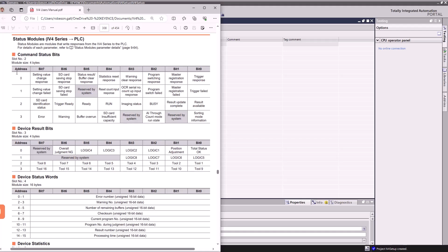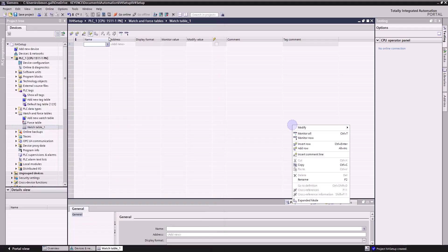So the inputs are actually a little bit, it's a little bit slightly confusing on the addresses. So these are 0, 1, 2, 3. In the PLC, this is actually going to be 4. So you got to keep track of that when you actually import your GSD file and create the IV4 as a module in there. So we're going to be looking at bits 4.0 and 4.6.